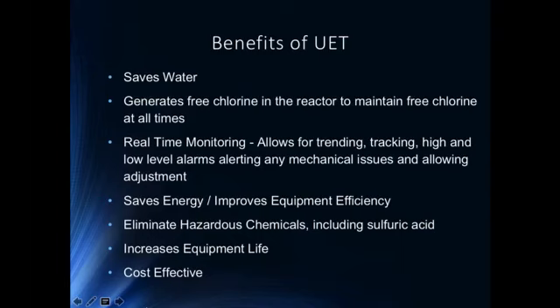So let's talk about some of the benefits. Obviously, we talked about saving water. We'll talk a little bit more about it in a second. Again, generating free chlorine in the reactor to maintain free chlorine at all times. That's a really big game changer when we start talking about biological control and Legionella minimization. The ability to constantly keep a free chlorine residual rather than trying to shock dose it.